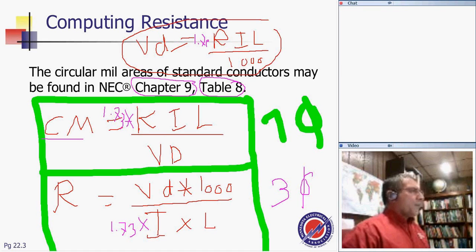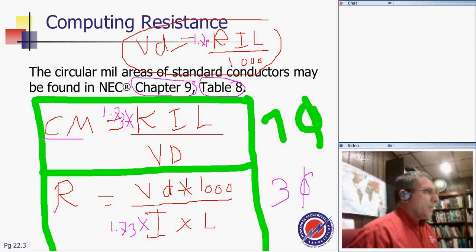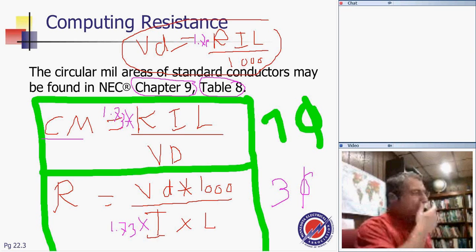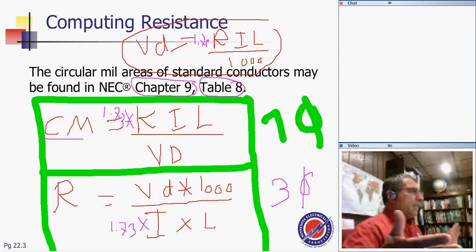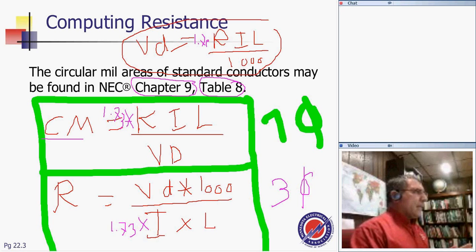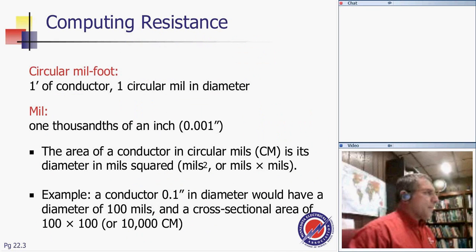Okay, we'll take a few examples, guys, just to explain it, but I want you to keep these in mind. You know that the longer the distance, the higher the voltage drop, the bigger the conductor, of course, if sizing. It makes sense. If I'm sizing a 500 kcmil conductor and I want to carry 380 amps, I can carry those 380 amps for a certain amount of distance. If I wish to go longer, then since the conductor stays the same, the amps basically have to go lower. So there's a calculation that we can do to find the amps, the conductor, the length, and so forth.